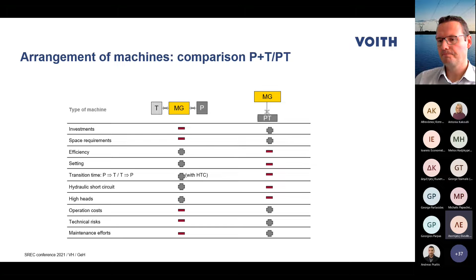It is because of cavitation and physical limitations that the unit typically needs to be below the lower tailwater by about 1/10 of the overall water level difference. This means if you have, for instance, a 200 meter head difference, the pump turbine needs to be about 20 meters below the lowest tailwater level. Hydraulic short circuit would give some more flexibility, as shown on the next slide. And the operational cost and the technical risks, of course, are less with a more simple solution of the pump turbine.